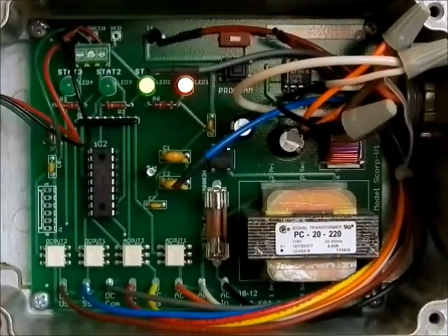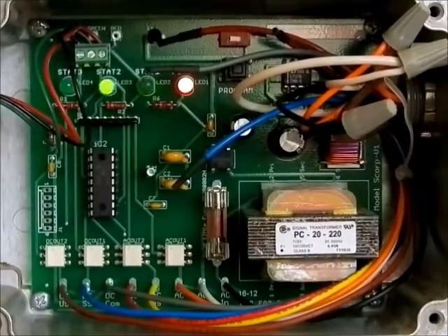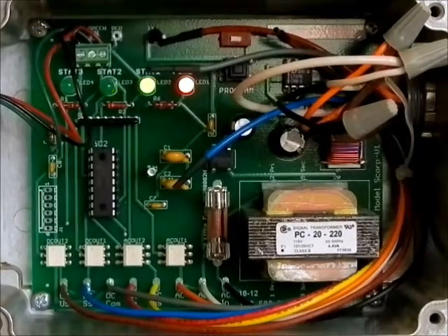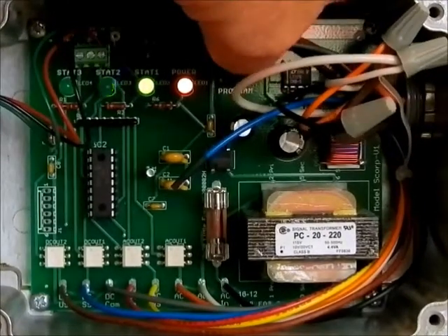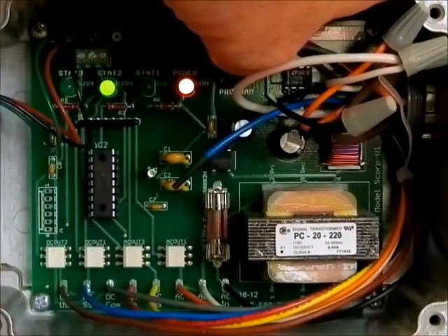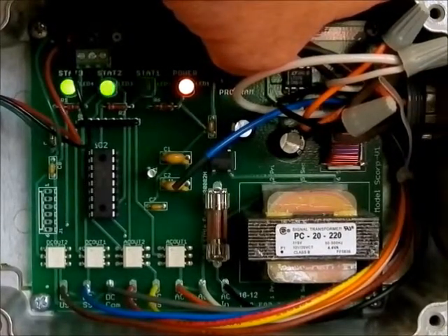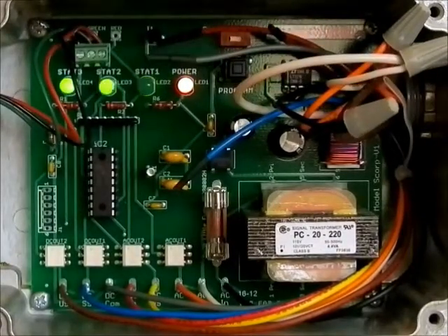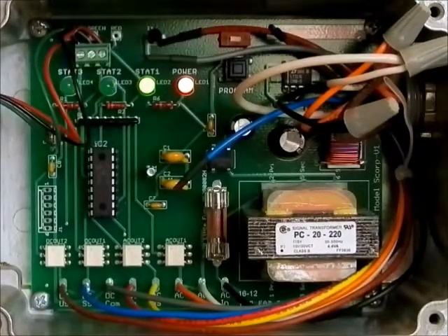There is a programmable underspeed output available. To program the underspeed set point, you should have your equipment operating at normal speed. You then press and hold the PROGRAM push button for about 6 seconds, and then release it when STAT3 changes to a slow flash. After about another 6 seconds, STAT3 will flash rapidly and then go out. The underspeed set point is now programmed.